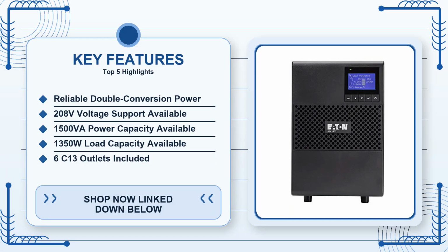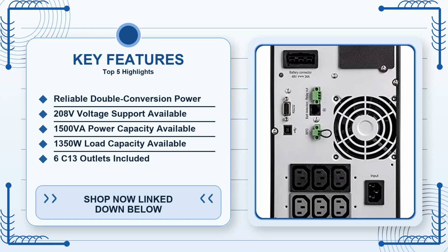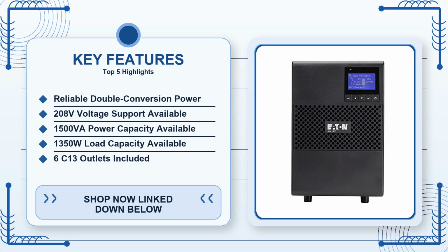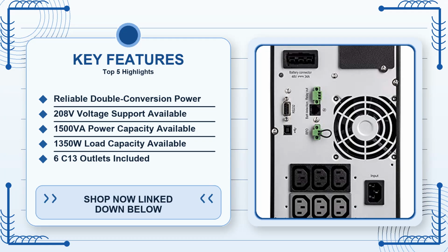One of the strengths that shows up repeatedly in real-world deployments is the true online double conversion architecture. Unlike line interactive models that switch to battery only when voltage dips, the 9SX runs the incoming AC through a rectifier, then back through an inverter, delivering a perfectly conditioned sine wave at all times.